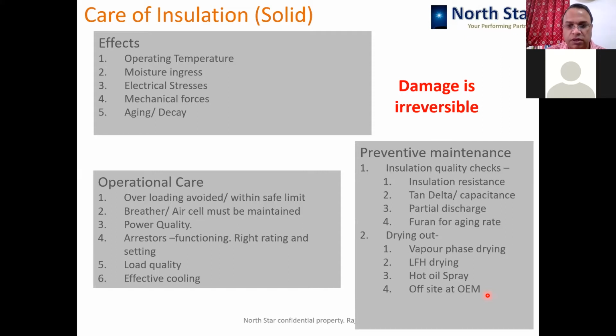That is to be understood by the fact that oil filtration is a very ineffective way of drying the insulation, and it takes a long time. Many times 15-20 days go into the filtration, and at the end you won't find that your insulation is dried out.